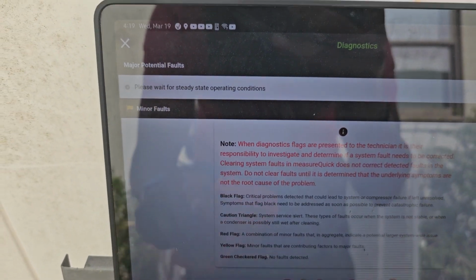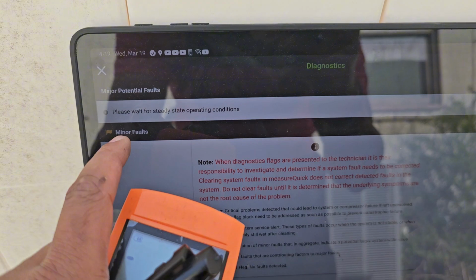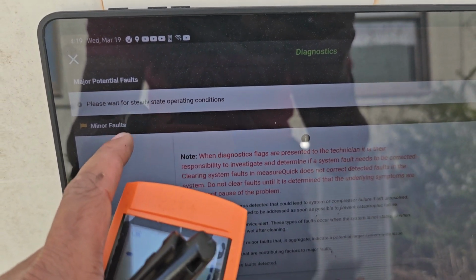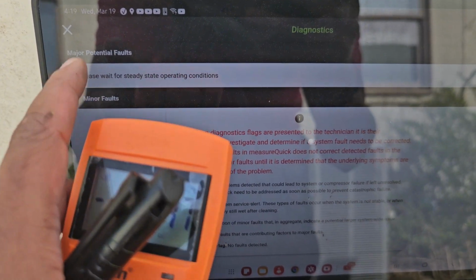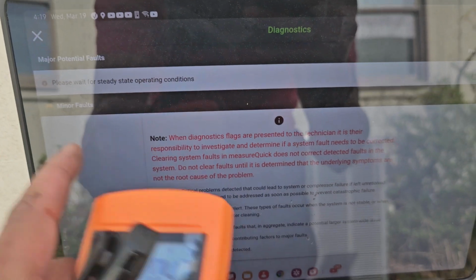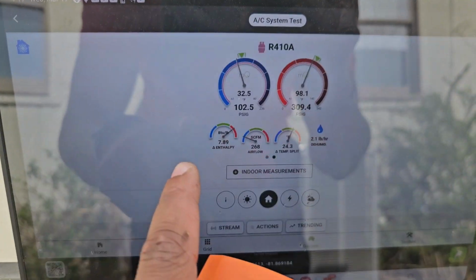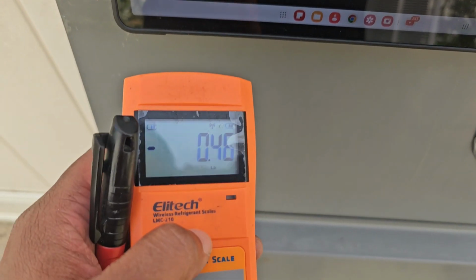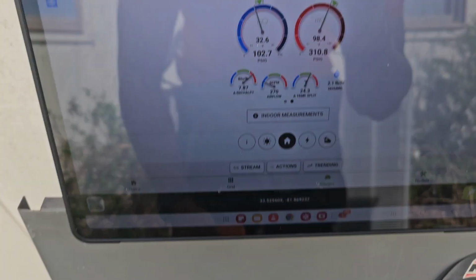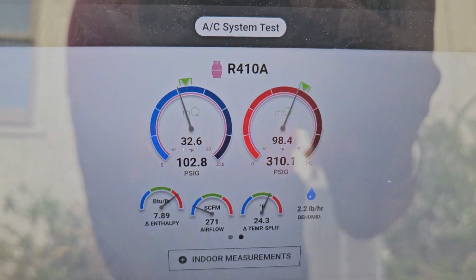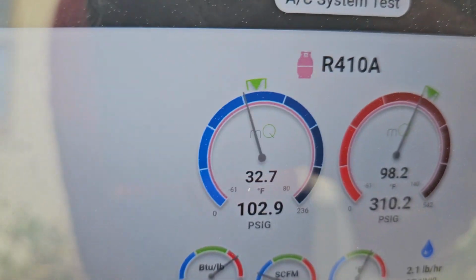It was showing I had 2 faults here: sensible capacity below 90%, and system potentially low on charge, or something along those lines. That was as I was dumping in a half pound, so we're already closer to that needle, closer to that needle.